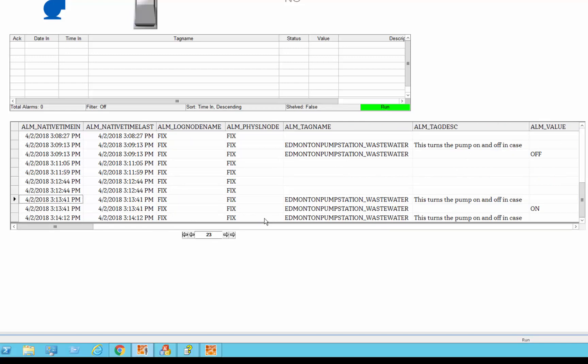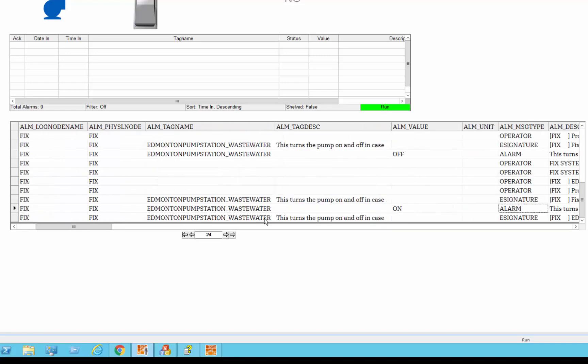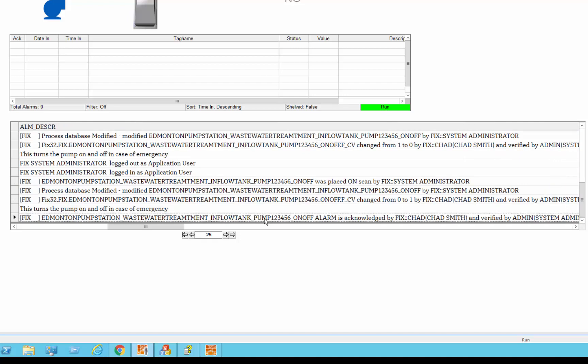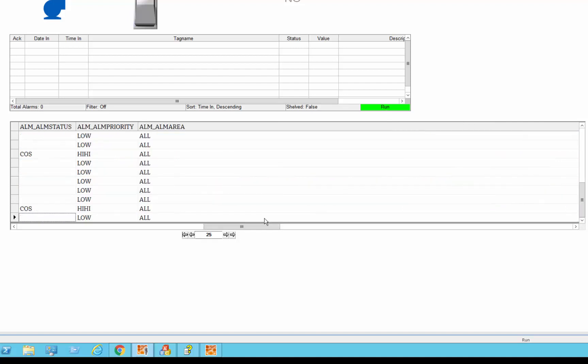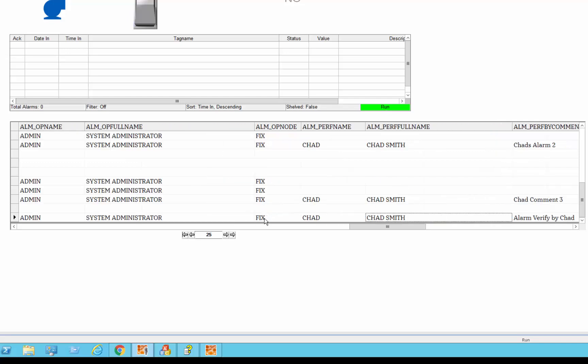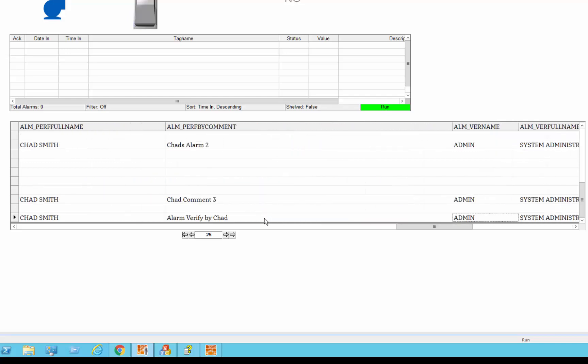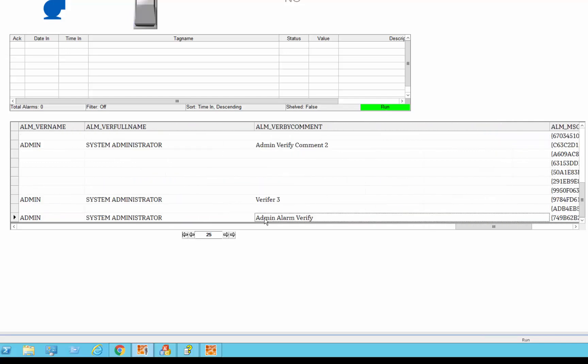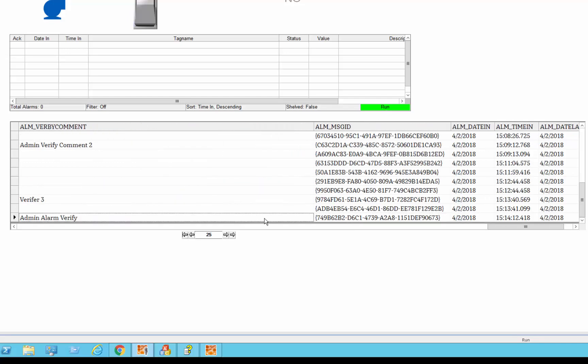...you can see that then we had an alarm happen, so the type of logging is e-signature followed by an alarm and then we did the actual acknowledge, which again had to be verified, you can see that's done there, and again the comments in the comment fields, alarm verify by chad, and admin alarm verify, so that...